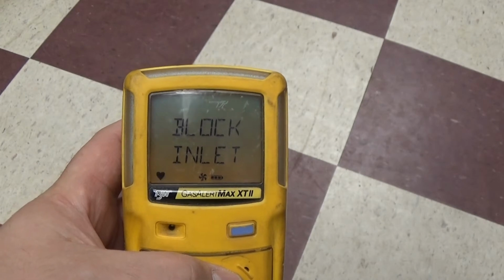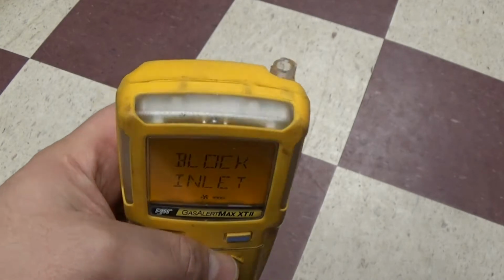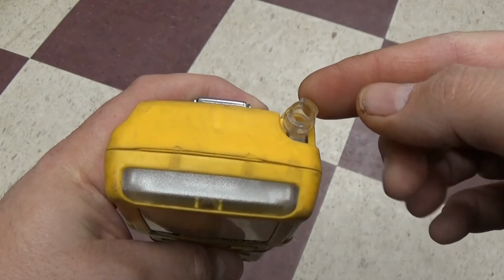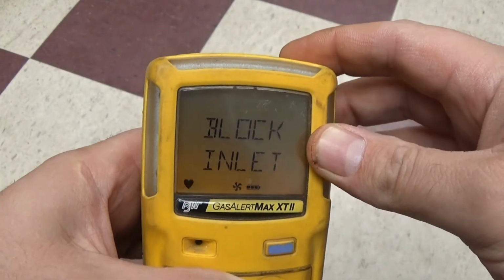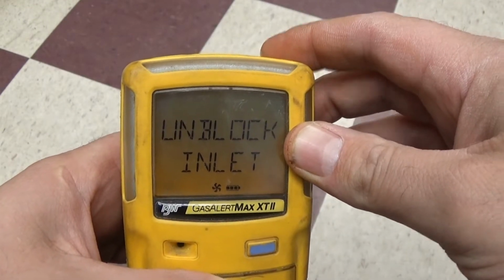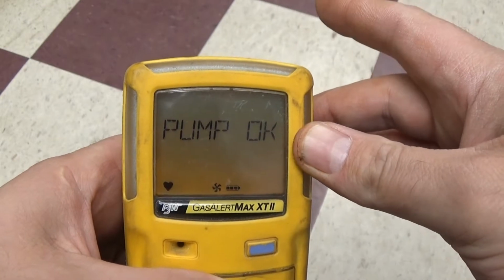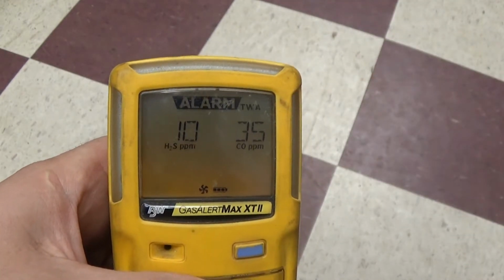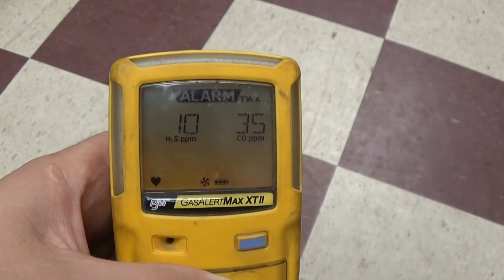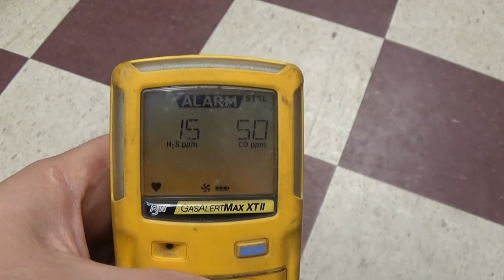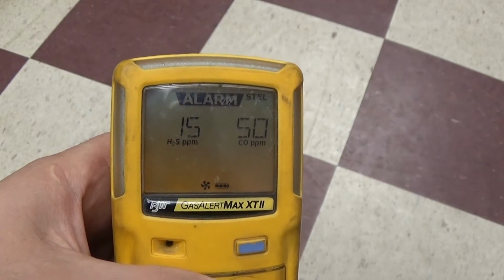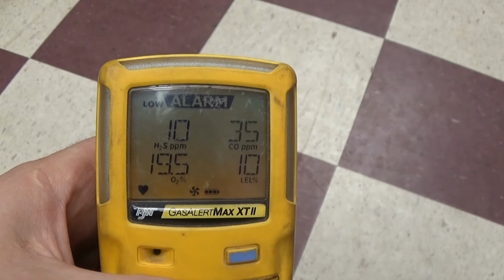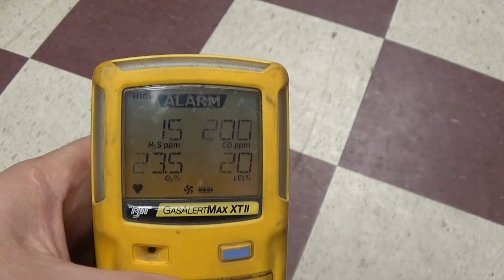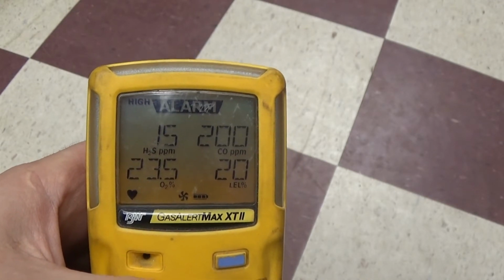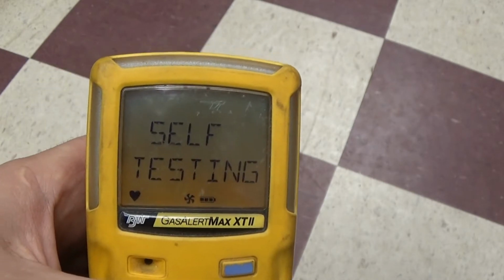First thing it's going to ask you to do is block the inlet. It's got a built-in pump, and this is the pump inlet here. Place your finger over it until it tells you to unblock the inlet. Take your finger off and it will start up its process. It will tell you the pump's okay, and then it's going to show you the H2S and CO high and low alarm. High and lows on all 4 gases that we're testing for.